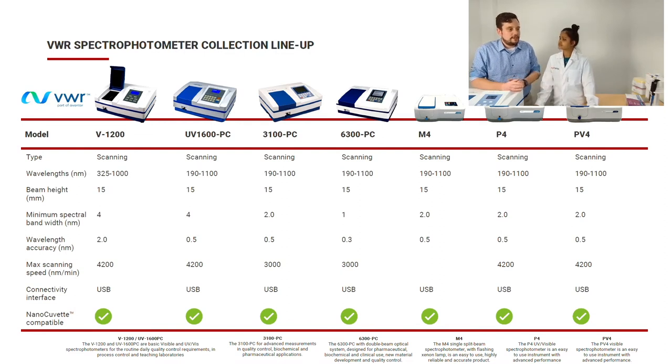So really a lot of data is available with this instrumentation. They use, as I mentioned earlier, the 15 millimeter beam height, so there is a cuvette just designed for that. So if you decide you want to test out different cuvettes, just bear in mind that you need to choose the 15 millimeter option.